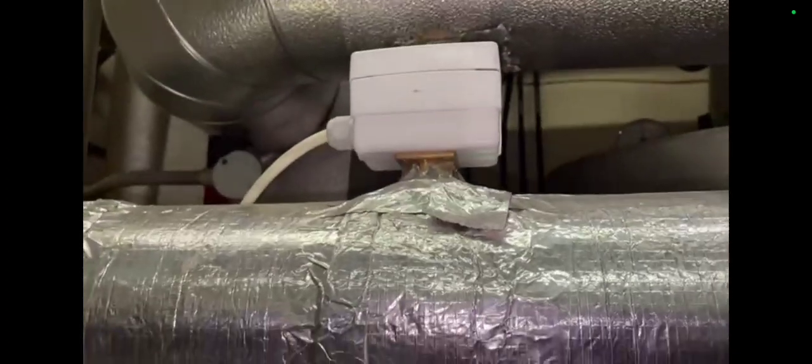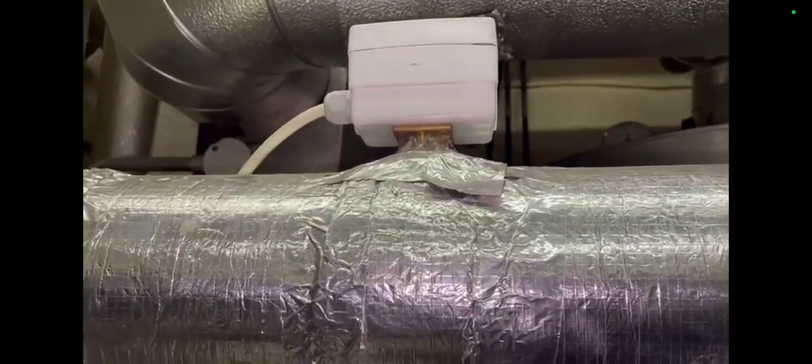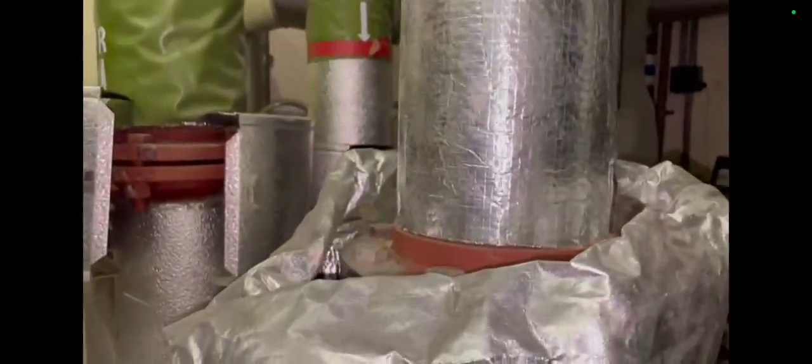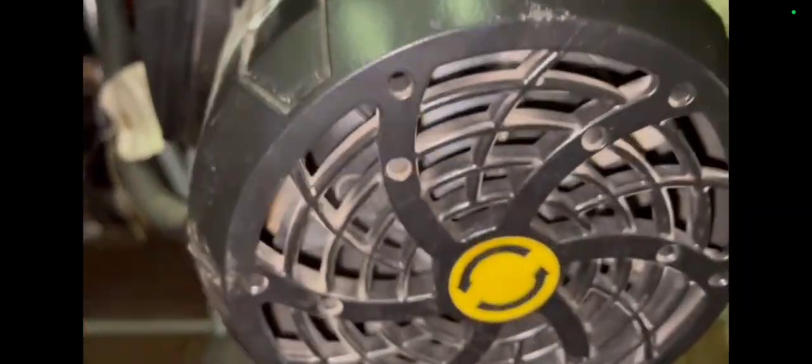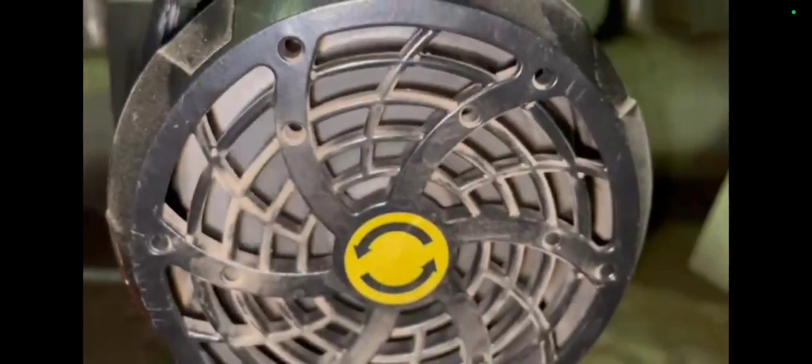I'll continually trace pipe work around. The flow switch there. Making sure valves are all open. These are my pumps. Top pump was switched off and then switched over to the other pump. The top pump, it's fairly new, so that one's probably going to have to be changed on guarantee or warranty.